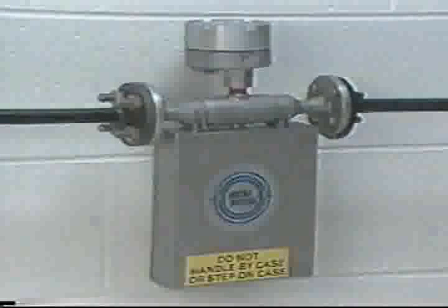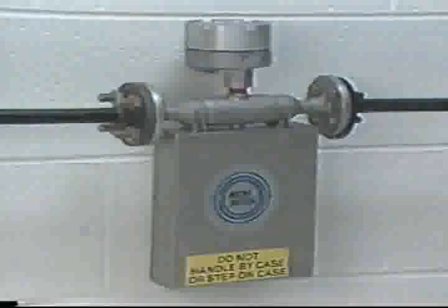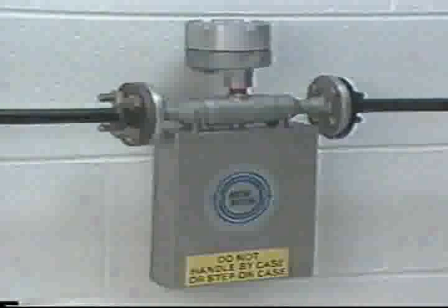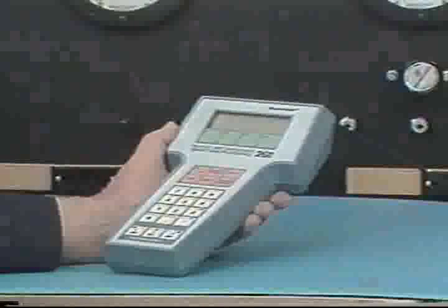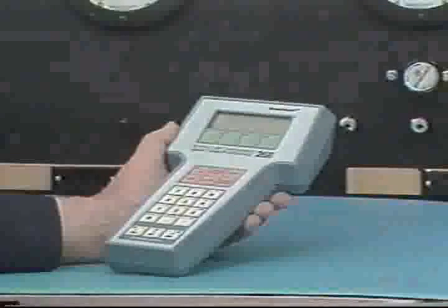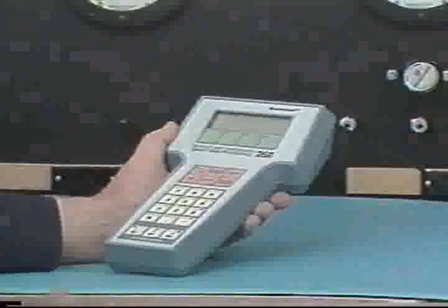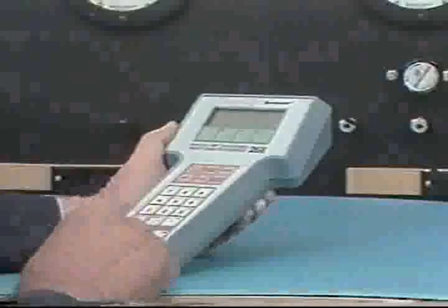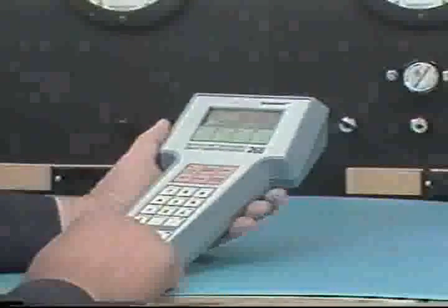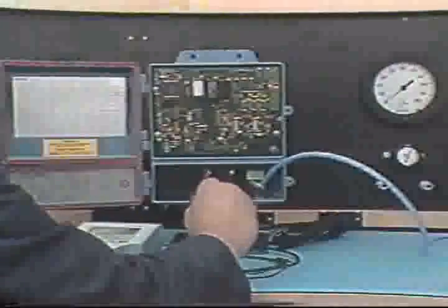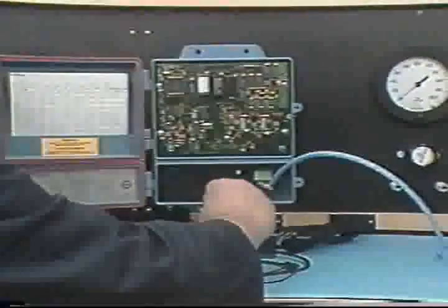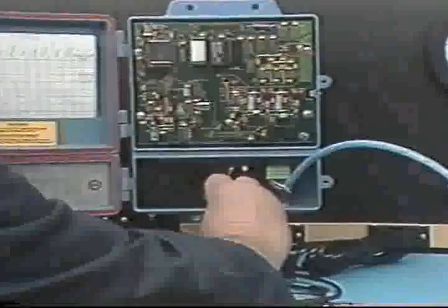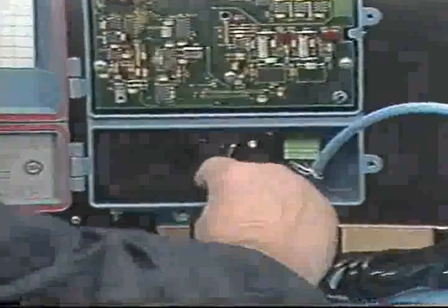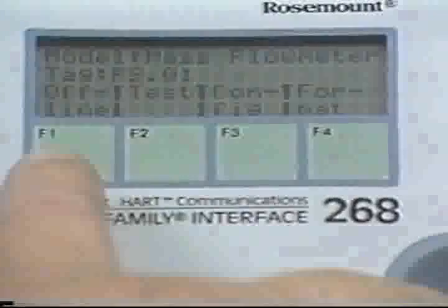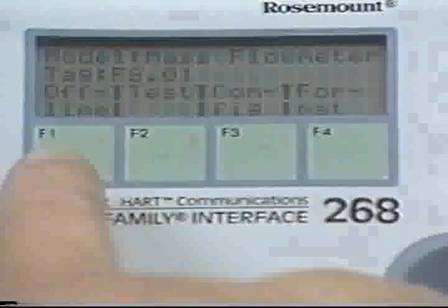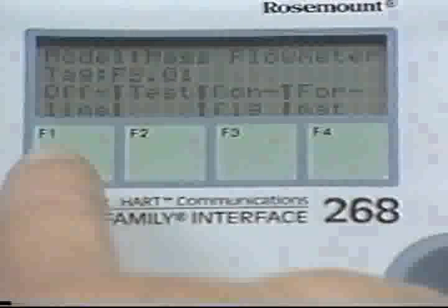Just like other calibration procedures, an input and output standard are required. However, because smart mass flow meters are digital instruments, they require a special communication device. This device or interface is required for configuration and calibration. The interface must be connected to the transmitter. It can be connected at any point in the loop as long as it's in parallel with the signal lines. Values can be input into the interface and downloaded to the flow meter.